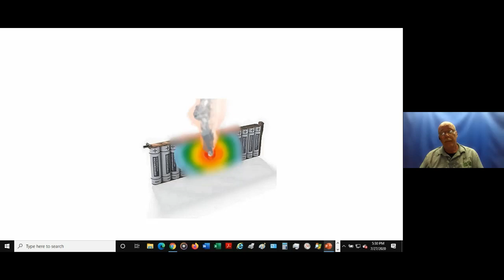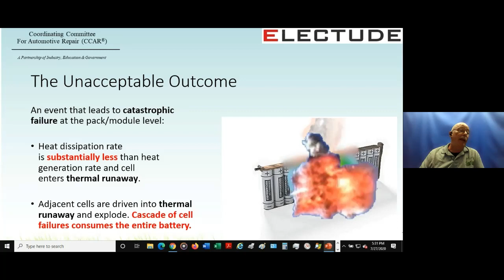So to recap, an abuse event: reaction within the cell creates additional heat and gas and the reaction zone expands. Heat dissipation rate is substantially less than the heat generation rate over time. The cell enters thermal runaway. Additional heat and gas are produced. The cell violently vents and explodes. Additional cells are driven to thermal runaway, and cascade failure takes the entire battery with it.